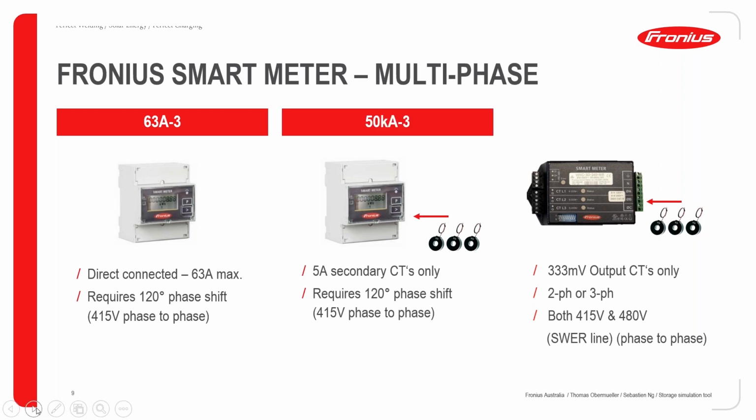And then you have your 50K smart meter, which is one based on CTs. And this particular one, you will need basically 5 amps secondary CTs. Compared to our 480 UL meter, which is also for our three-phase sites, this one you need 300 millivolt CTs.